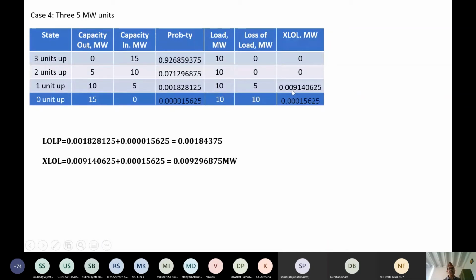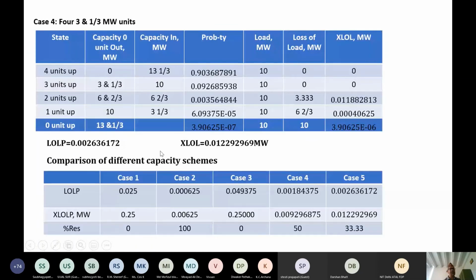This and this, putting them together, adding them together, will get 0.009296875. So this is the case when we have a 50% reserve margin. Okay. And then we have a case 5 where we have 4 units of 3.33 megawatt. Why do we choose this 3.33 megawatt? Because by choosing 4 units, we'll have a 33.33% reserve margin.